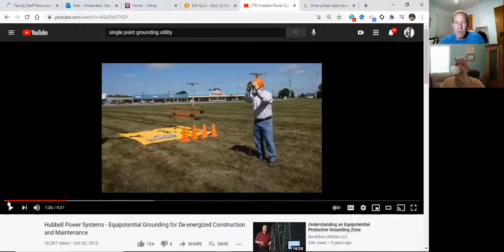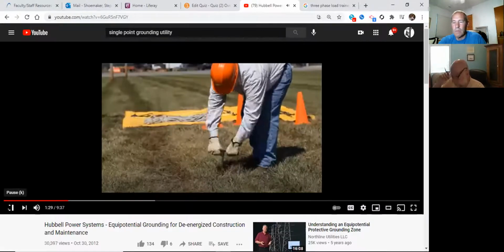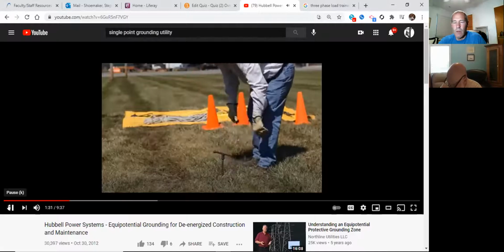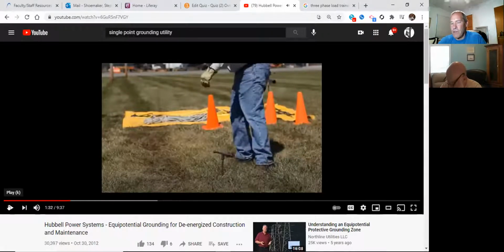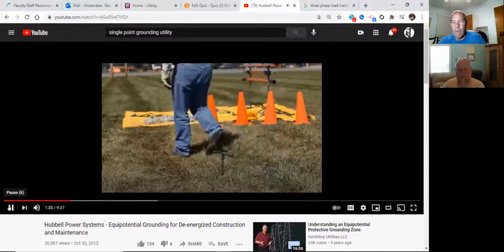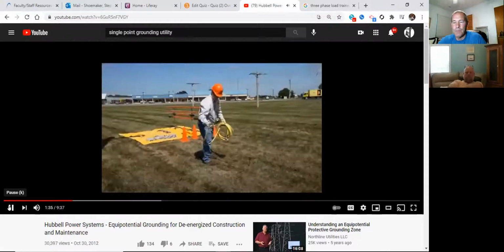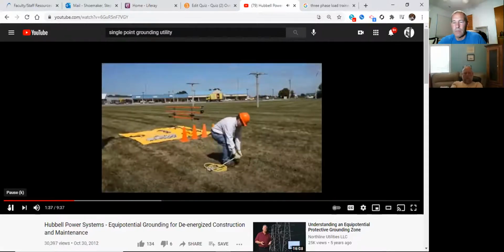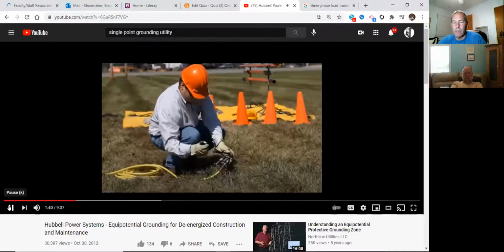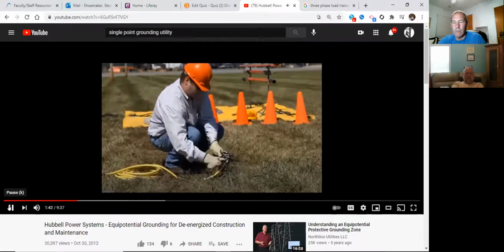All right. So install temporary ground rod. The spiral threads pull the 6-foot copper-clad rod into the earth for full length. Okay. So guys, if you get this thing going halfway down, you hit a little bit of hard ground or a root or something, don't stop. Find another location. It's got to sink that far into the earth. Use it fully. Contact as a low-resistance ground. This now makes the bronze T-handle a good attachment point for connecting our first grounding set clamp. To make sure it's tight, a screwdriver may be used through the eye-screw.